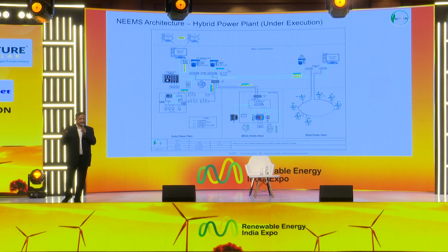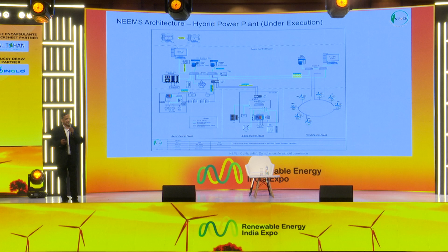Having a battery energy system in place helps mitigate that. In case there is excess generation, you can store it in the battery and discharge it when the solar output is lower. Typically, with wind turbines, during the monsoon months, generation is much higher, and sometimes the excess DC capacity installed in terms of solar inverters needs to be curtailed. Using battery systems, you can reduce those possibilities of penalty and harvest the energy for a longer time.